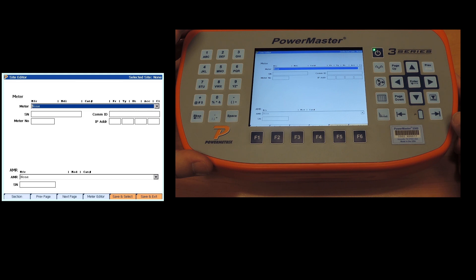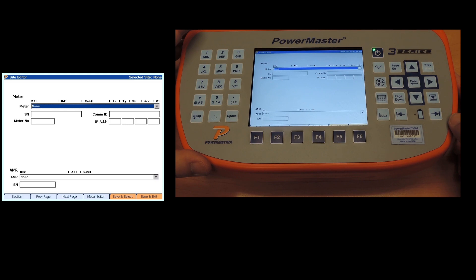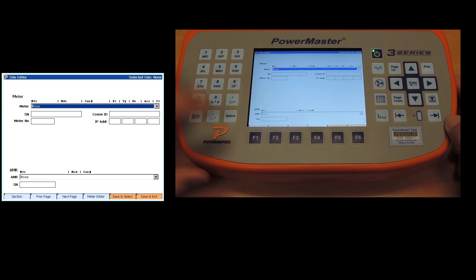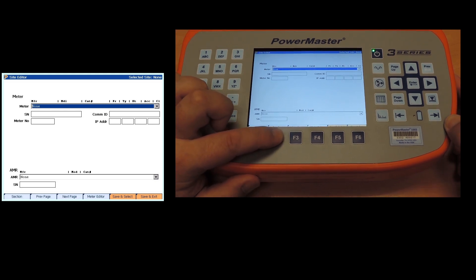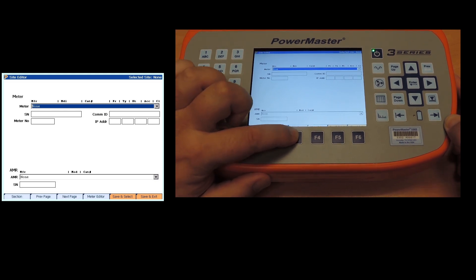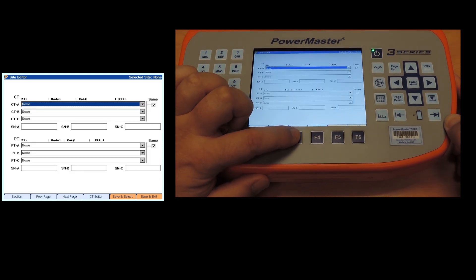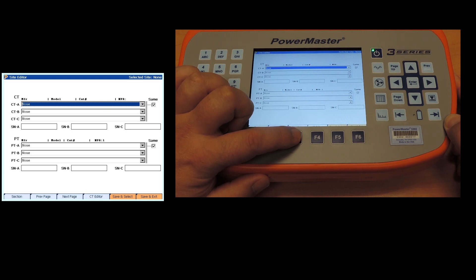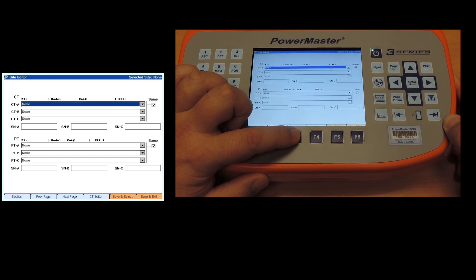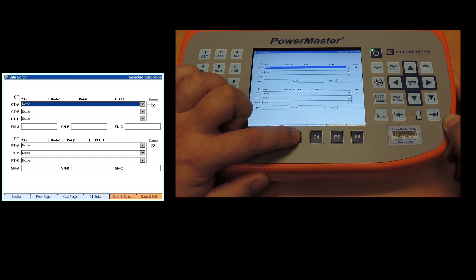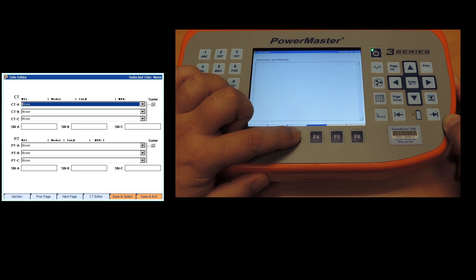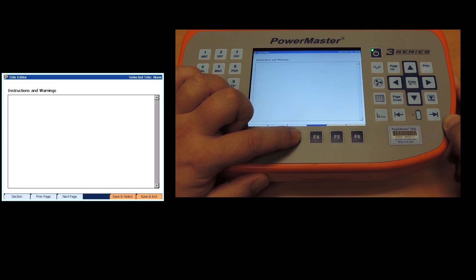You can put in the serial number, meter number, etc. Gives you the same options with your AMRs. Next page, CTs and PTs allows you to put in any information for those. However, if you do not have the exact information from the nameplate, leave it blank. It'll test it and calculate it that way. If you put in the incorrect information trying to get the correct ratio, you could cause a test failure.